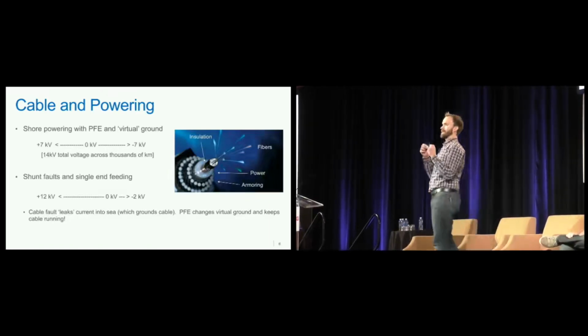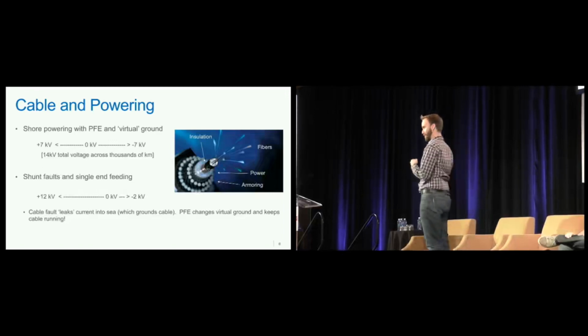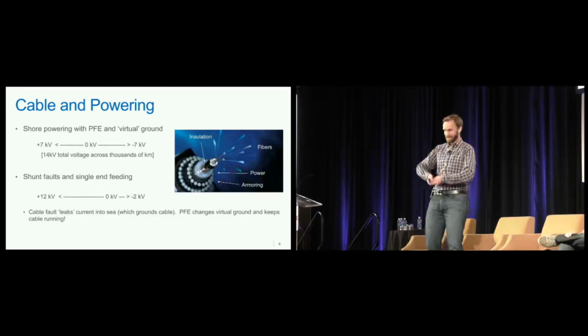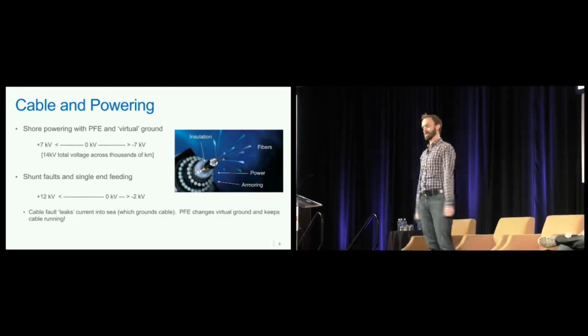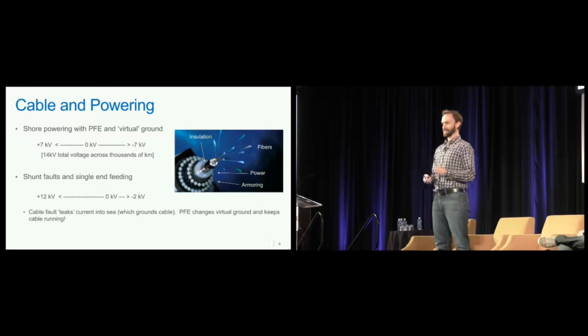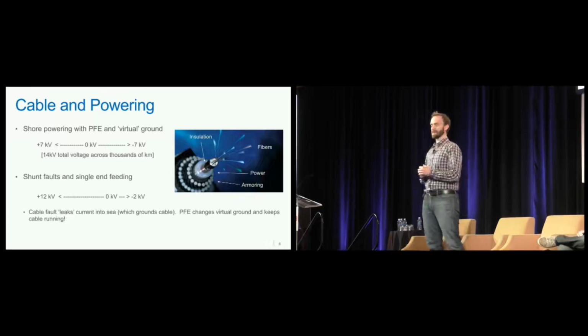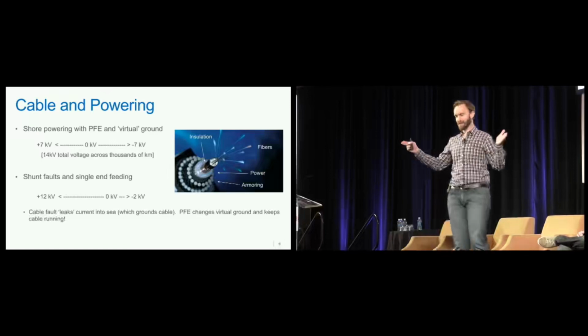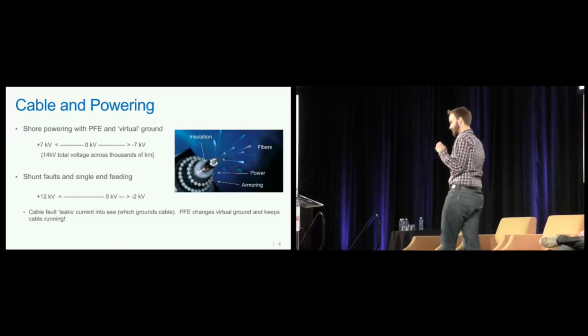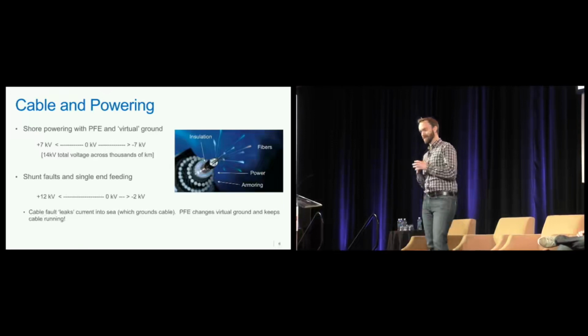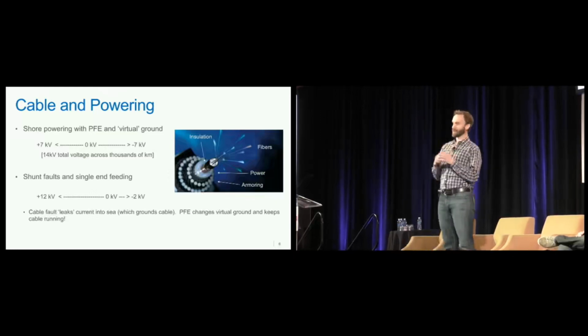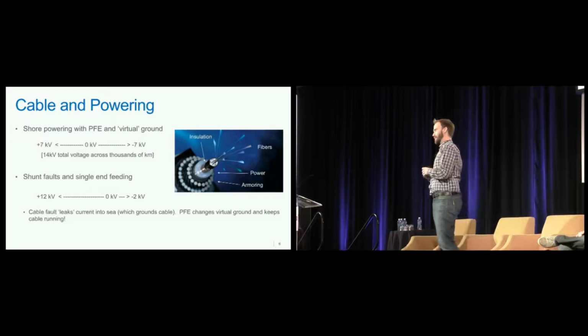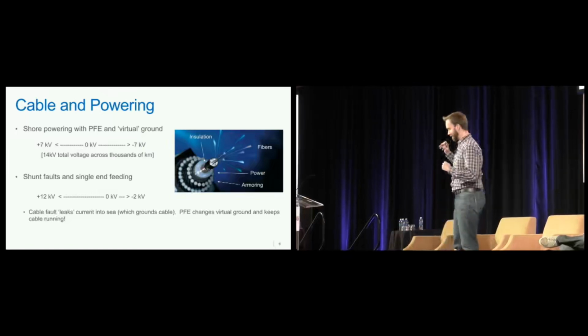Fixing a cable requires calling a boat, which comes out, fishes it up, takes it apart, and puts it back together. If it's unscheduled, it can take weeks, sometimes a month for the boat to get out there. So having the power feed equipment change the ground when the cable is compromised is one reason these systems have good uptime and availability. But you can only handle one fault at a time — if two happen, you're toast. So when they do happen, alarms go off and you get the boat out as fast as possible. That's, in a nutshell, how the cable is powered.